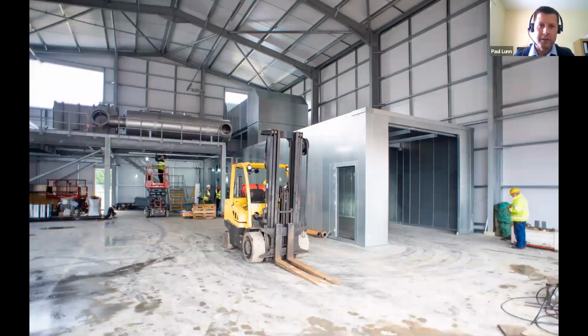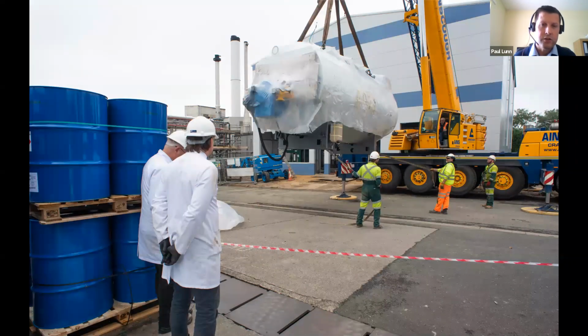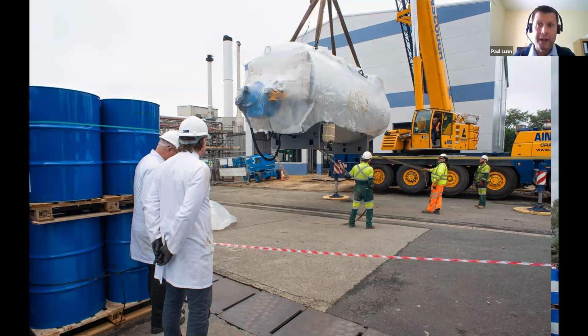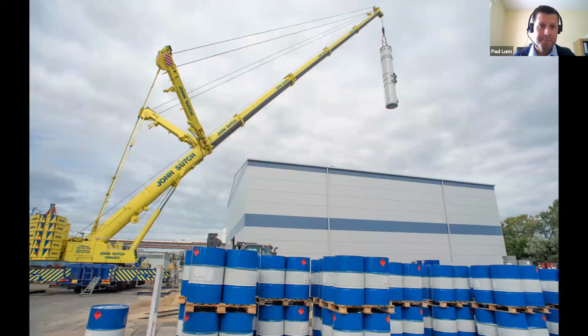We moved through to installation of the equipment: a soundproof enclosure for the engine and generator set, and the large exhaust system you can see in the background, which will take the heat to one of our high efficiency boilers. All the boilers specified for this project are high efficiency units, fitted with modulating gas burners, modulating feed, and economizers. One of them can also take the high temperature exhaust from the engine and use it to generate steam for the site.